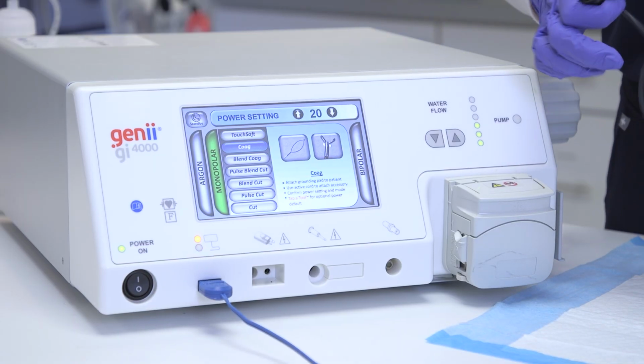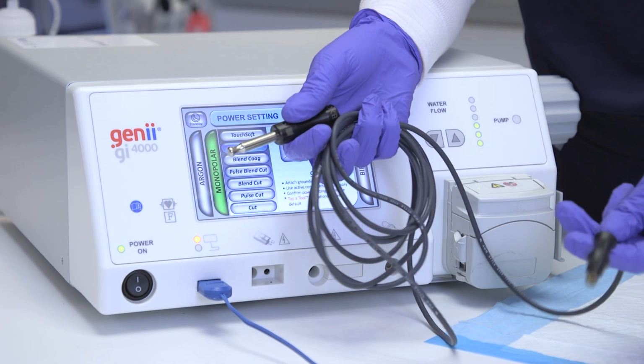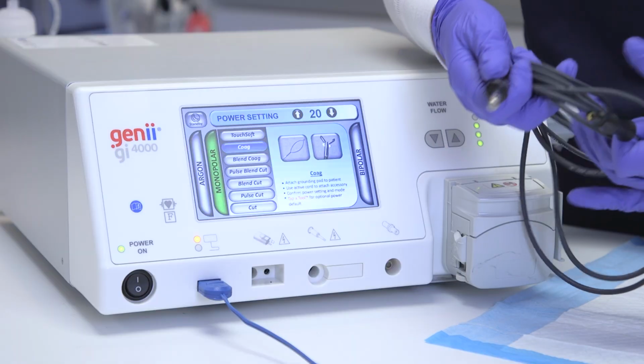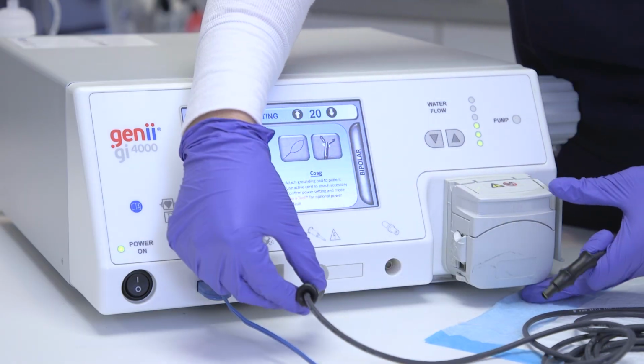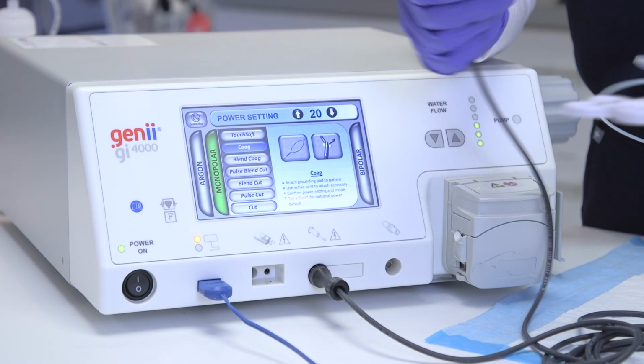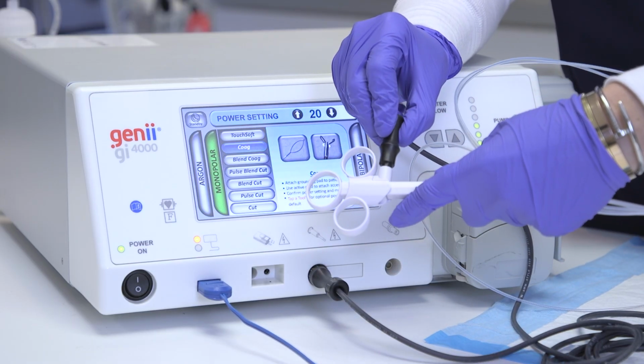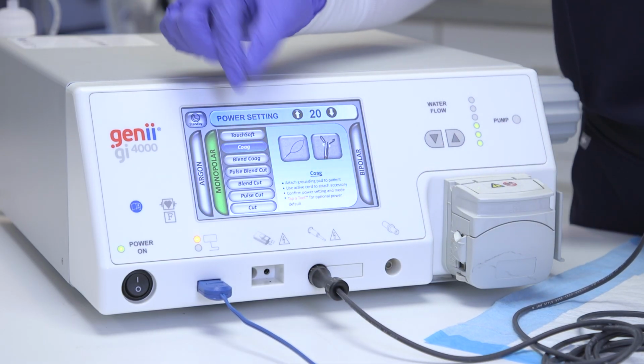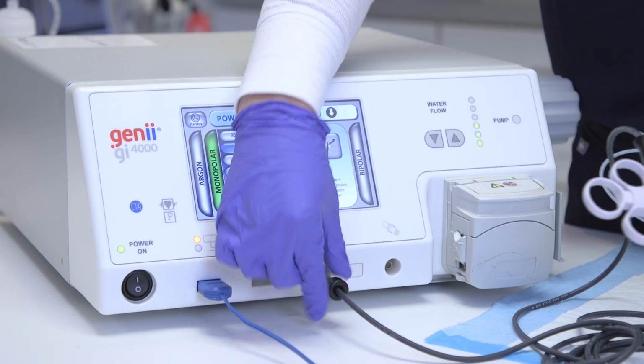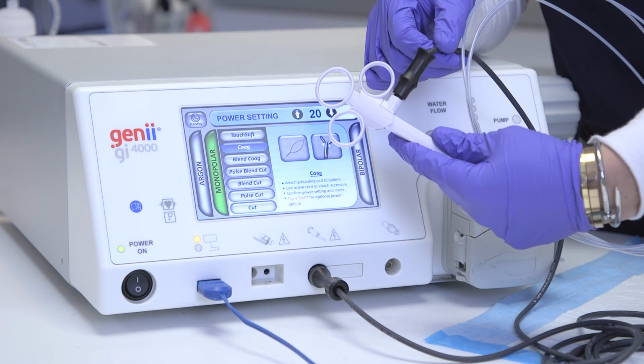For the Monopolar method, we require the use of a reusable Monopolar active cord. You'll plug the Monopolar active cord into the ESU, as well as the other end to the accessory chosen. You'll want to hear it click. You'll verify that it's plugged in firmly to both the unit and the accessory.